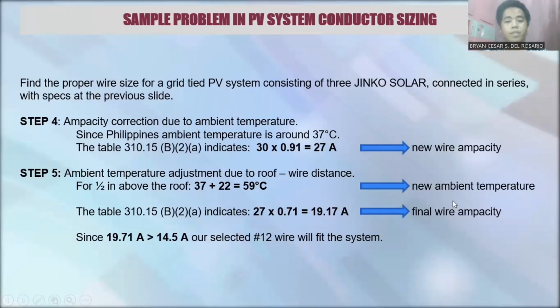That's our new ambient temperature. Using table 310.15(B)(2)(a), we check our new wire ampacity of 27 ampere against where 59 degrees Celsius falls, to find its multiplier.